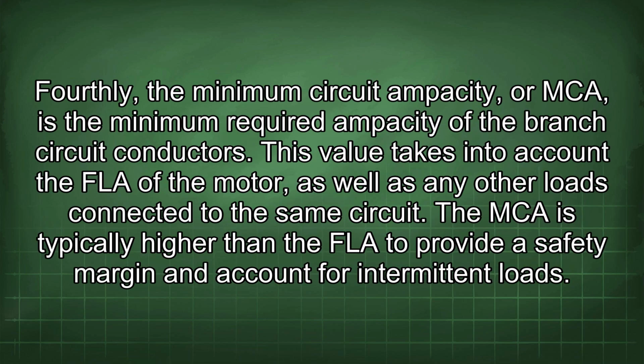Fourthly, the minimum circuit ampacity, or MCA, is the minimum required ampacity of the branch circuit conductors. This value takes into account the FLA of the motor, as well as any other loads connected to the same circuit. The MCA is typically higher than the FLA to provide a safety margin and account for intermittent loads.